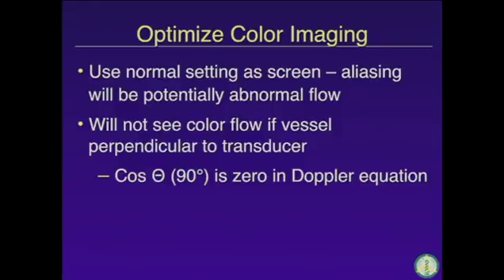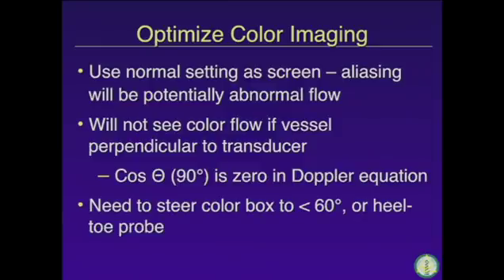Now remember that you won't see color flow if the vessel is perpendicular to the transducer, and that's because the cosine of theta, which is 90 degrees if you're perpendicular, is 0 in the Doppler equation. And we're not going to go into the Doppler equation any more than that, but if your transducer is perpendicular to the vessel, you may not see any flow, and there's plenty of flow there. So you need to steer the color box to less than 60 degrees, and that's our normal standard. If we have less than 60 degrees, we can get a fairly accurate peak systolic velocity. And if you can't steer that color box, you may need to heel toe the probe, so rock it back and forth until you can get an angle that's less than 60 degrees.